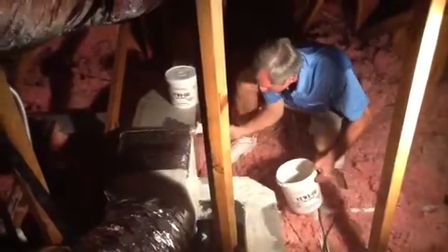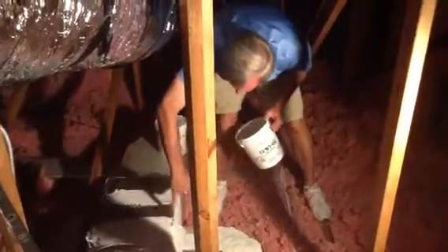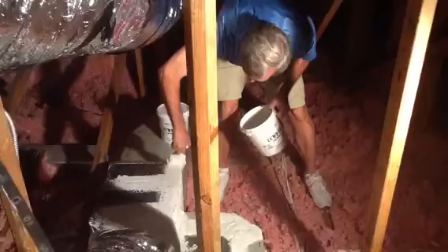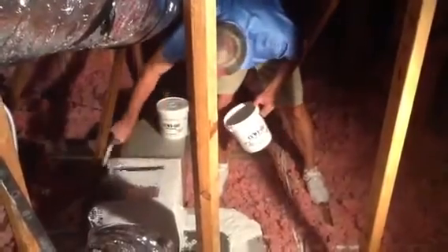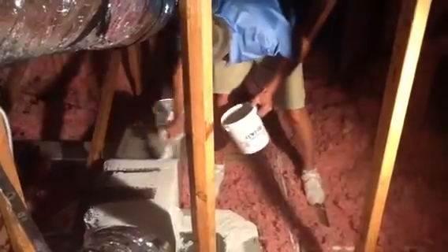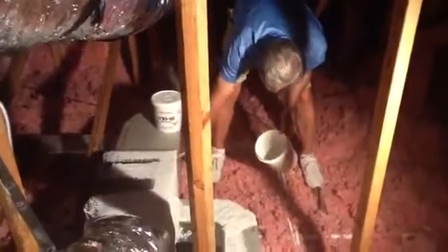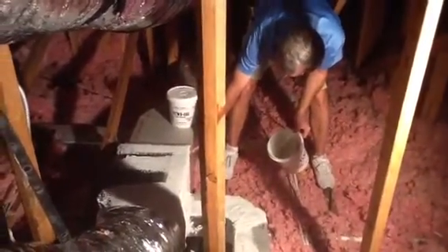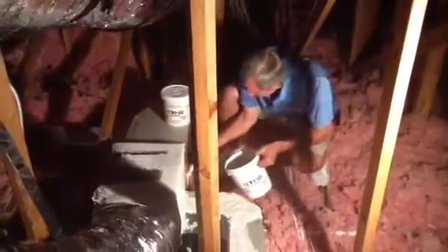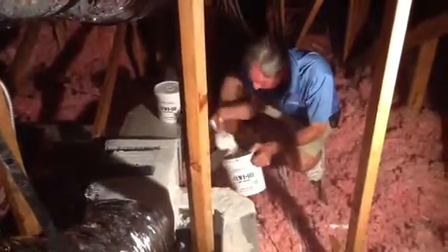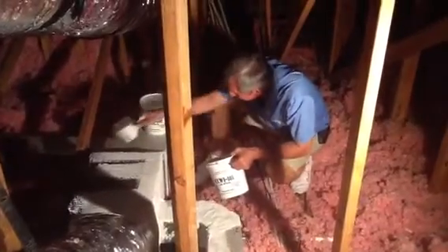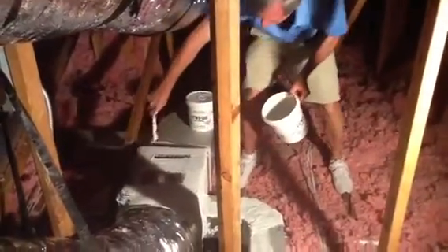I'm going to do one section here. See all these taped joints? Everything the guy's taped has to be mastic once again. Very important—this ductwork is probably from 1987, so think about that, guys. This duct system is already 15 years old, and it's in pretty good shape too. When these folks are spending lots of money for high efficiency systems, there's no reason why you shouldn't do it better. See how it's got a tape seam here?